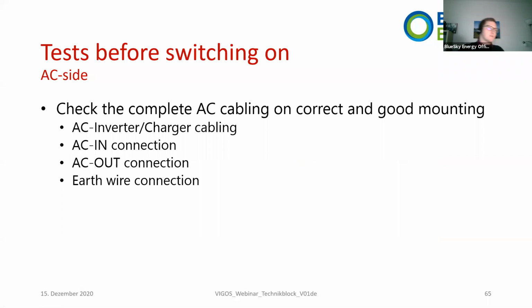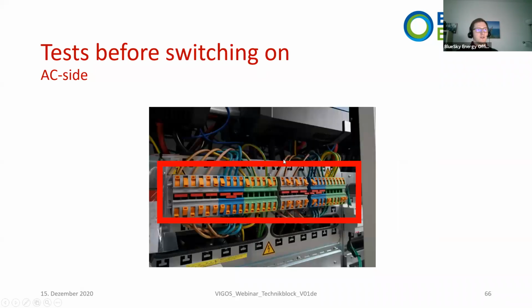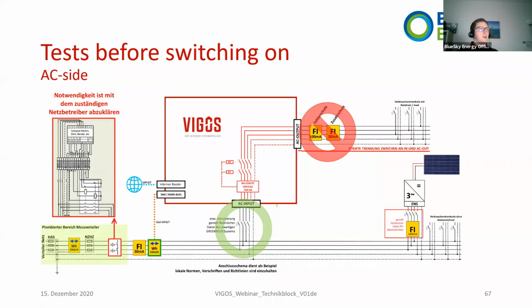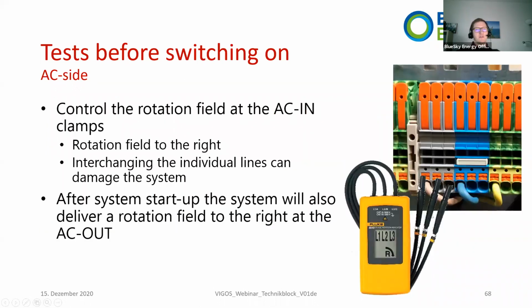When you start up a system, when you commission it, please always test the whole thing for good and correct mounting. So the AC cabling, AC in, AC out, and earth wire connection is really important. All the connections you have done here on the AC panel, please just make sure they are done in a good way. Test before switching on. We recommend that when you switch on the AC in cabling, you can already measure the rotation field, which needs to look to the right. I hope this is an understandable definition.